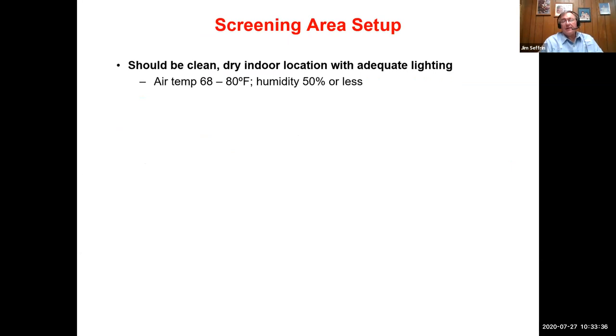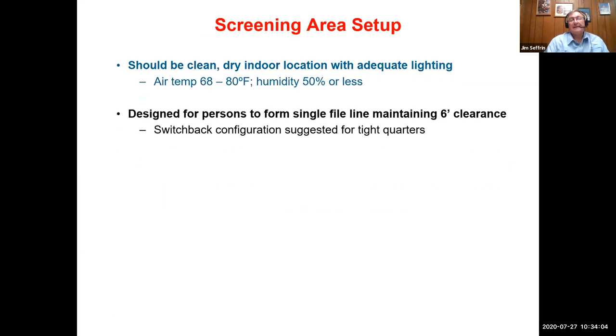Now, if you do engage in this, this is not something that you just set up in a parking lot or at an outdoor stadium and start taking temperatures in any weather conditions or at any time of the year. In order to have a properly and effective screening area set up, this area should be clean and it should be a dry indoor location with adequate lighting. The air temperature should be between 68 to 80 Fahrenheit and the humidity 50% or less. The screening area setup should be designed for persons to form a single file line maintaining 6 feet of clearance.